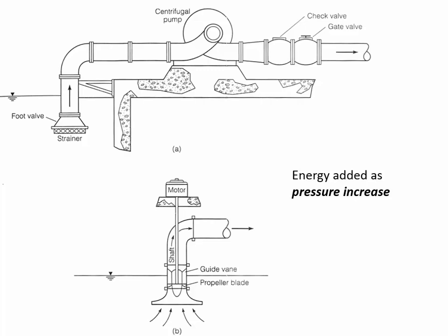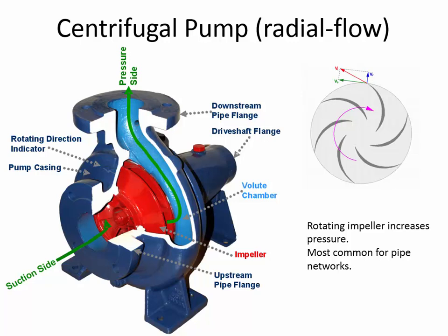Yeah, how is the pump actually adding the pressure? It's adding the pressure because it's accelerating the water inside of there. And you'll remember that when we were talking about convective acceleration, that increases in acceleration increase the pressure. And so it's basically having to do with the shape of the blade, and there's going to be more pressure on the outside edge of the blade than on the inside of the blade. So it's similar to how a wing creates lift. And as that impeller is spinning around, there's more pressure on one side of the impeller than on the other.